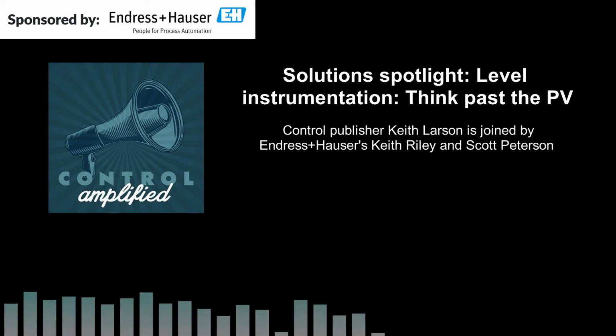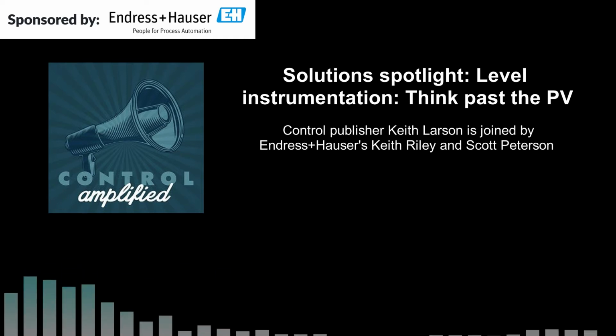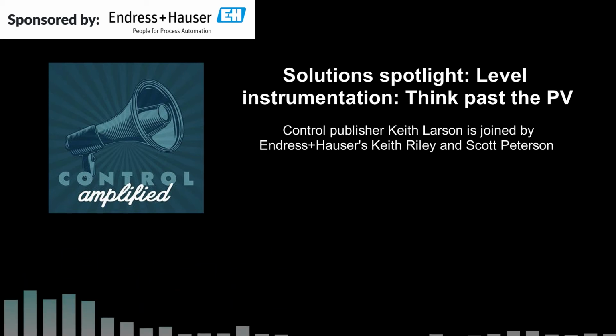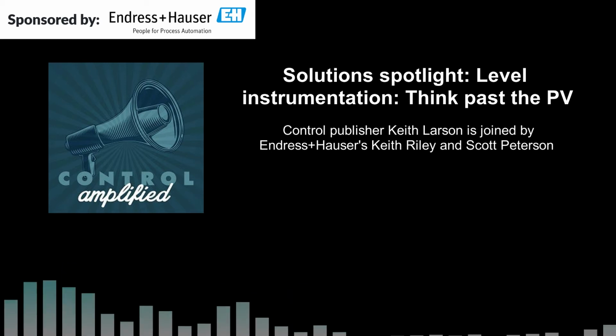And that's where some of the changes today come in. You'll see different functionality like proof test wizards, easier ways of proof testing. Take a point level switch, for example. You can have multiple ways to do your proof testing. Some of it's as easy as pushing a button, which runs it through a cycle. Sometimes it's a magnetic coupling that does it. And as I said, you have your proof test wizard, which really addresses that systematic failure. Think of the dozens, if not hundreds, of instruments that are in an area with an SIS. Each one of them is going to have a slightly different proof test procedure, and no technician is going to have them all memorized. So then he has to resort to a manual and back and forth reading it and hoping he doesn't get interrupted or something else happens.